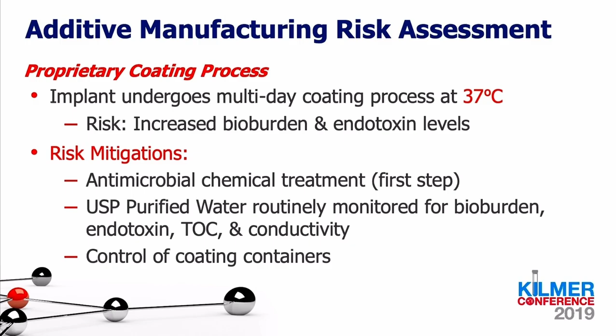And then the final consideration is there is a coating container that we use, an HDPE container, which we had tried to source pyrogen-free. We were unable to do so in the size that we needed. So we actually worked with the manufacturer of the coating container to ensure they implemented cleaning steps and provide a certificate of this cleaning with every lot that is provided to us. And with every incoming lot of containers, we do an endotoxin test to ensure that it's of appropriate quality.